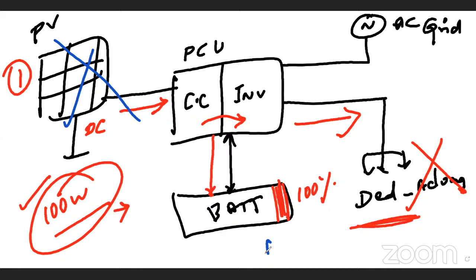Imagine a scenario where there is no solar power, but the battery still needs charging or the load needs power. In such a case, the second priority, the auxiliary AC grid supply, is given as input. At this time, the entire device works as a normal home UPS. The incoming power is converted from AC to DC by the internal circuit, which charges the battery, while AC also gets bypassed to the loads. This is the working principle of an off-grid solar system.